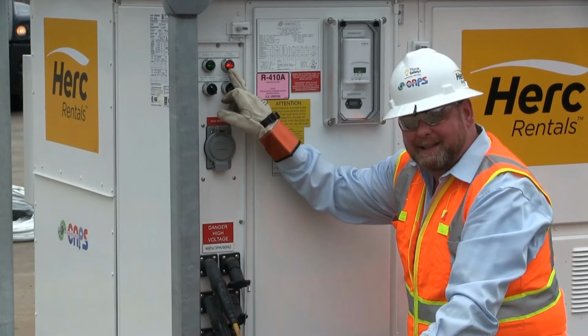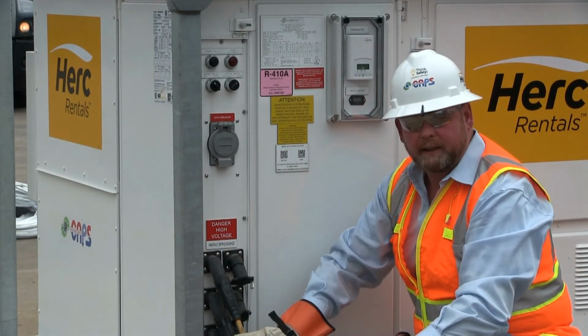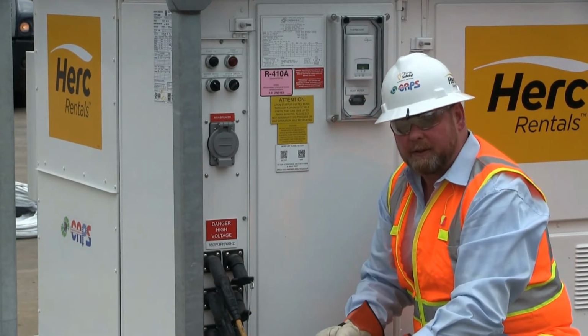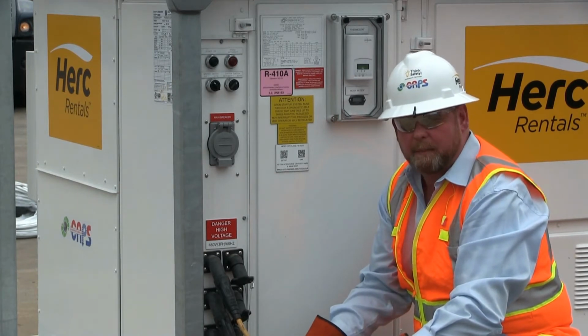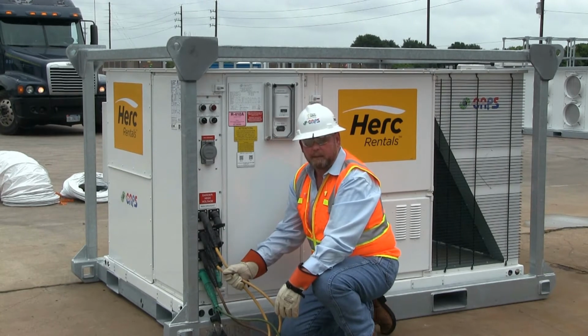We're going to lock out and tag out our power. We're going to shut the breaker off here, and we're going to have to change two of the cam locks here. Please note you never change any of the cam locks here as long as the power is energized. Reverse two leads in our incoming power.